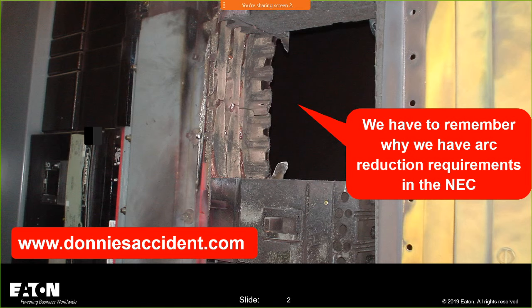Nice tool. Thanks, Tim. Is there an assumption for over 1,000 volts that it just clears too fast to need arc energy reduction? No, you're into a different world when you're above 1,000 volts. We can calculate arcing currents. We can use IEEE 1584. It's just not a code requirement at this point in the National Electrical Code.